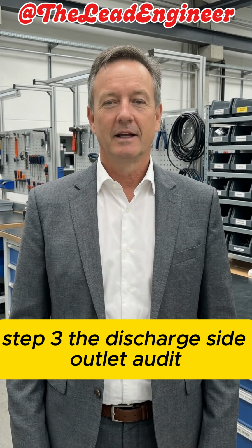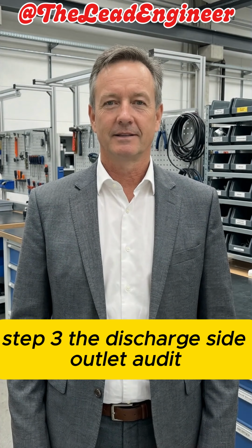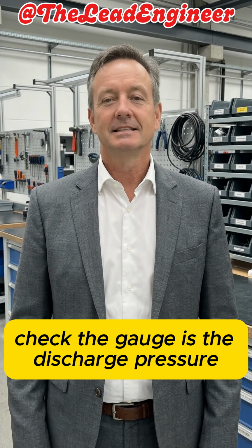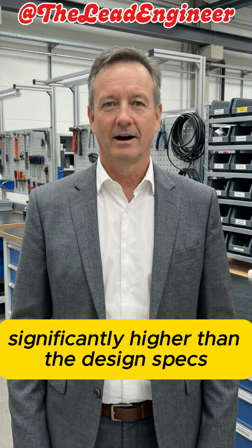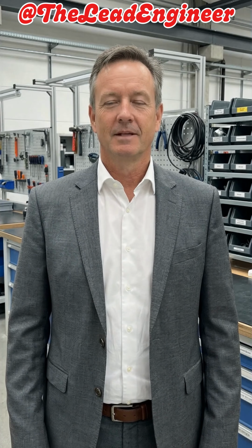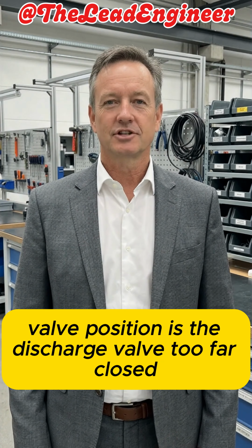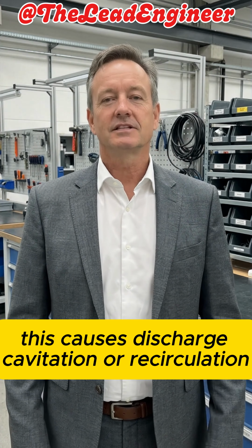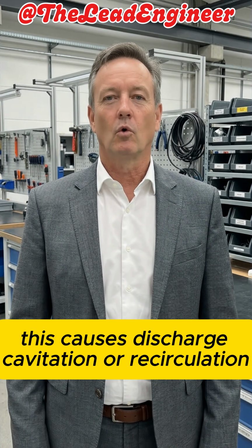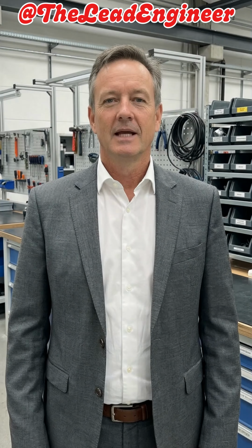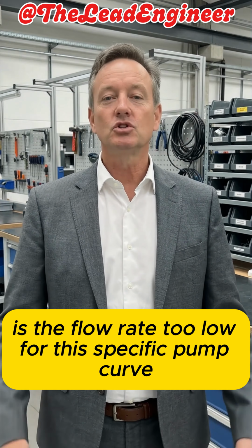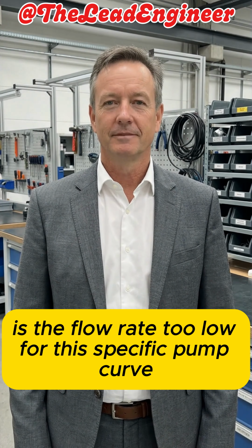Step 3. The discharge side outlet audit. Check the gauge. Is the discharge pressure significantly higher than the design specs? Valve position. Is the discharge valve too far closed? This causes discharge cavitation or recirculation. Check the flow. Is the flow rate too low for this specific pump curve?